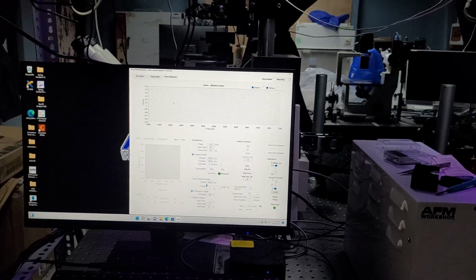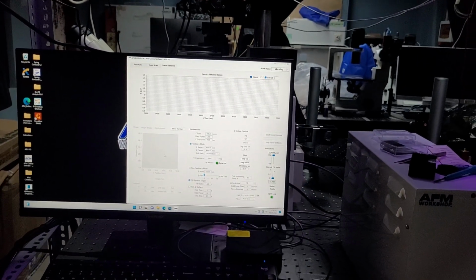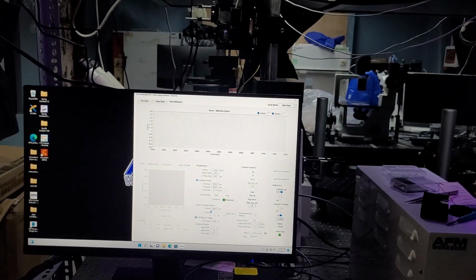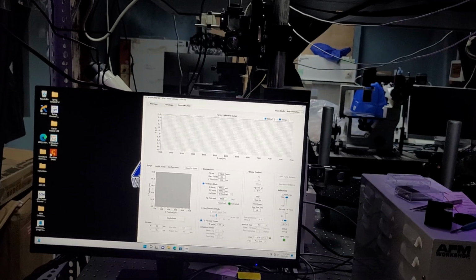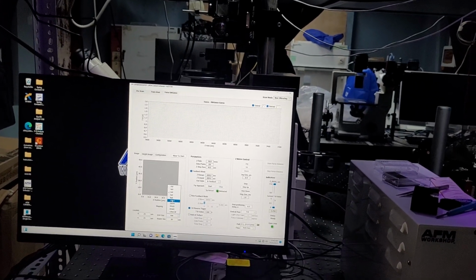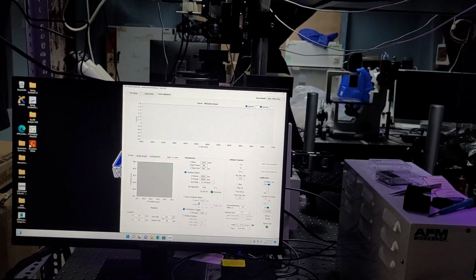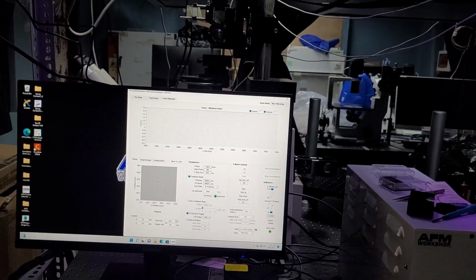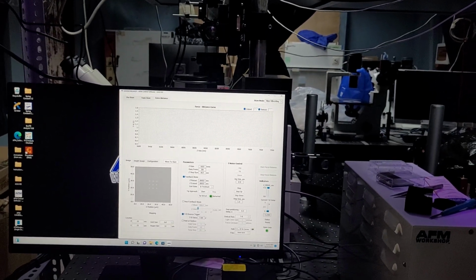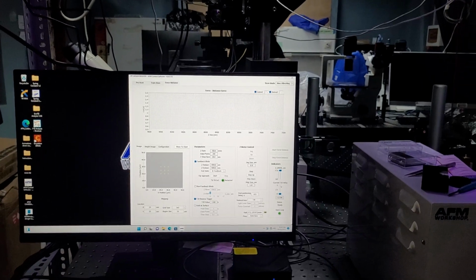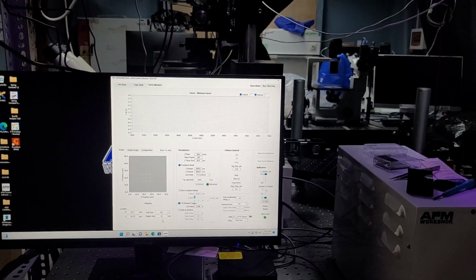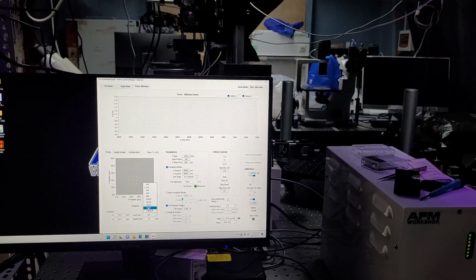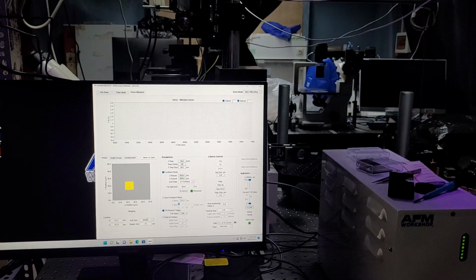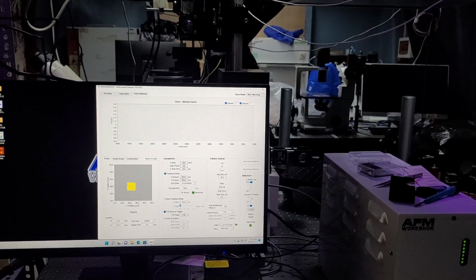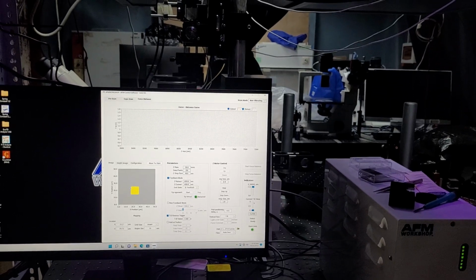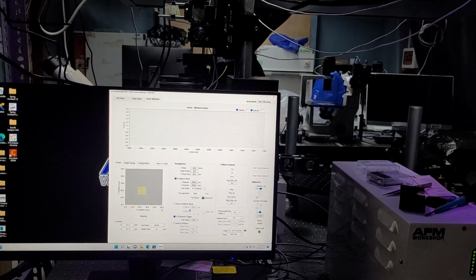This is where you're able to take a non-vibrating mode image here, and then you can create a, if I go ahead and set it up like this. So if you took an AFM image in non-vibrating mode, then you would get that image here. And then from there you can set up a mapping, single point, you can choose your grid size. So if you wanted to, you could take a 64 by 64, where each one of those will just go down and take a force distance curve at each point. And so this can be very useful for force mapping.